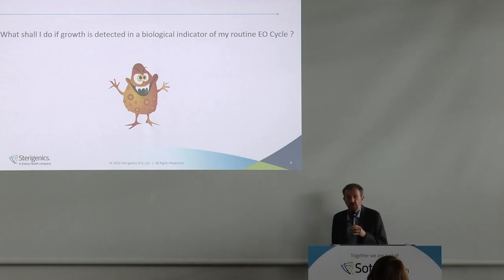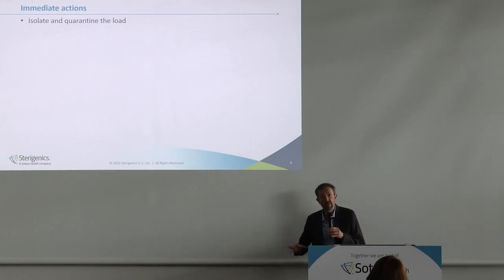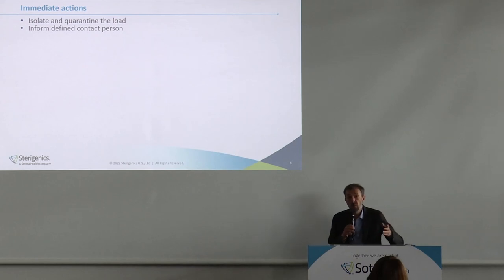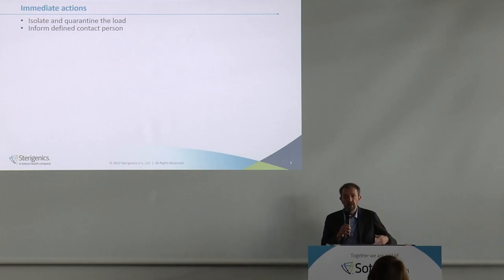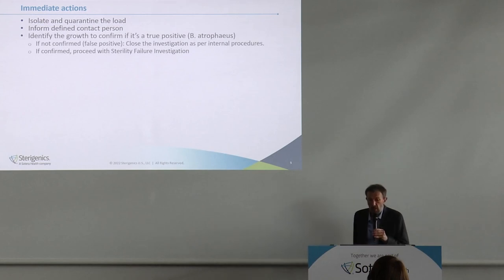I have a positive BI — it may happen. What is the first reaction needed? Don't go into panic mode; it's not necessary and will never be helpful. The first thing to think about is obviously isolating the load and making sure it cannot be sold as sterile. The isolation and quarantine of the load is really the first action. Then we need to contact the sponsor immediately and let them know there is an issue and the load might not be released. This has to be communicated operatively — we cannot wait a day.